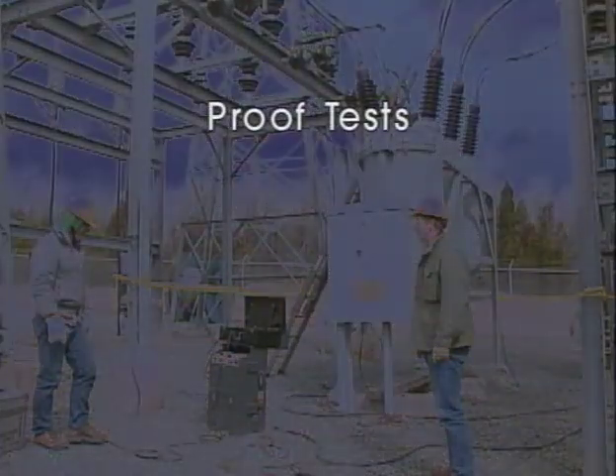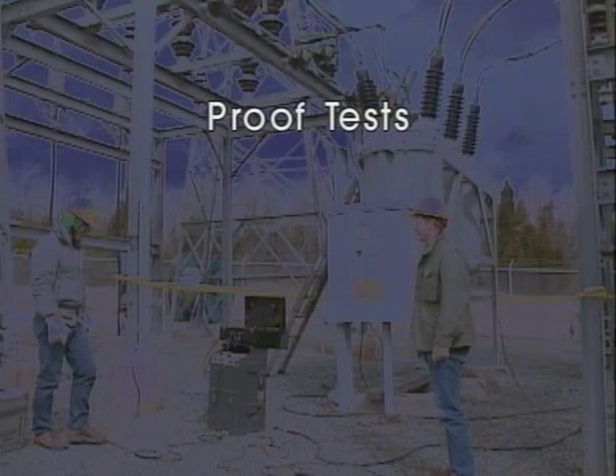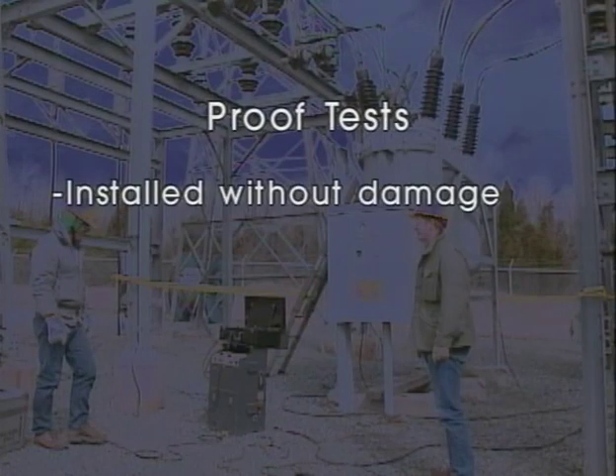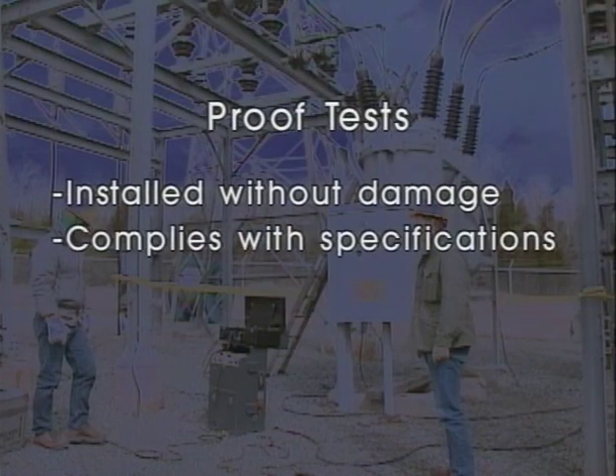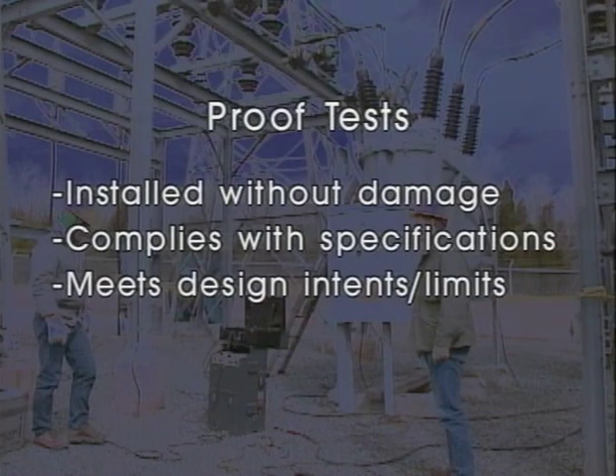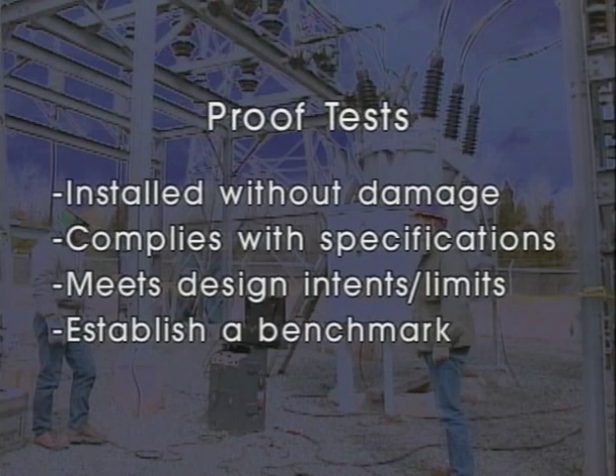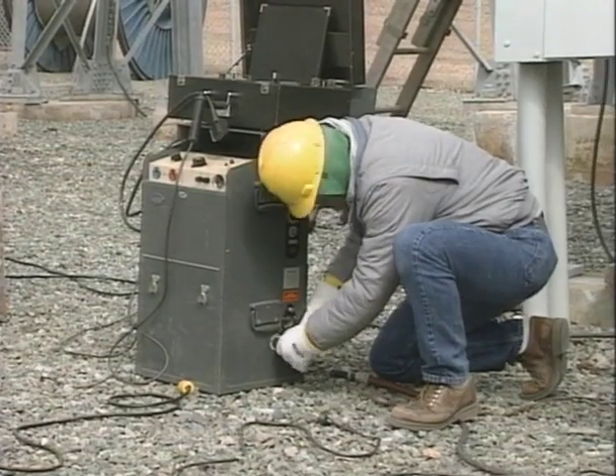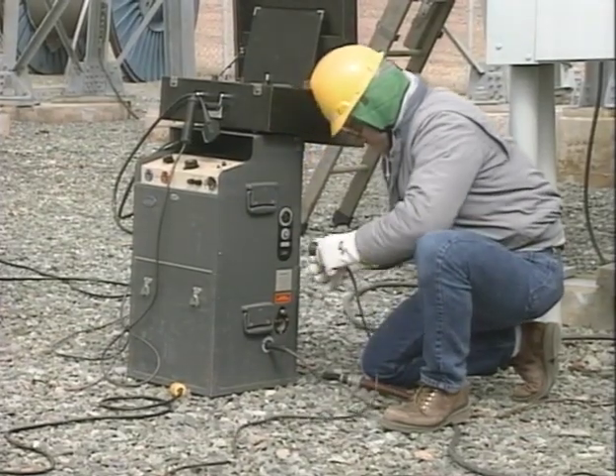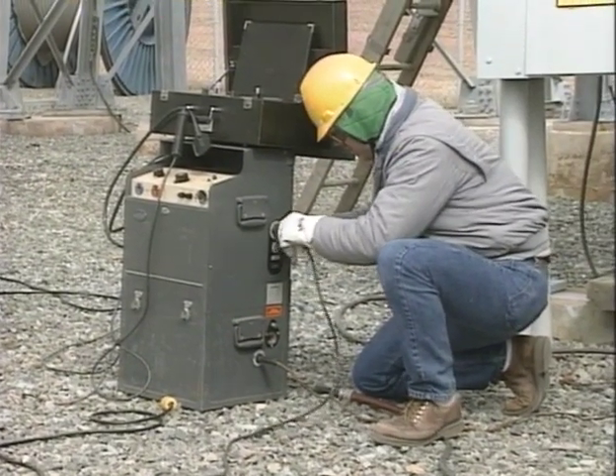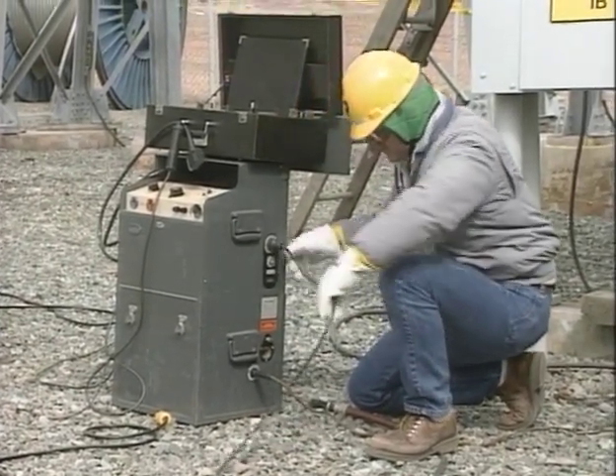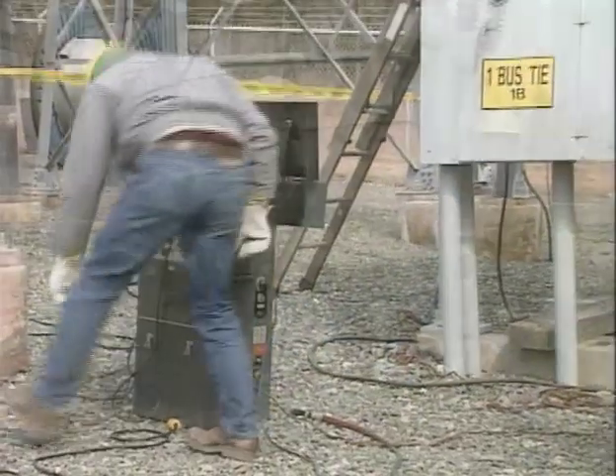In general, proof tests are the tests that are performed on a new circuit breaker to make sure that the breaker has been installed without damage, that it complies with the specifications, and that it meets its design intent and limits. Proof tests also establish a benchmark for future tests. The same tests that are performed on new circuit breakers are also typically performed during maintenance and testing of breakers that have already been in service.